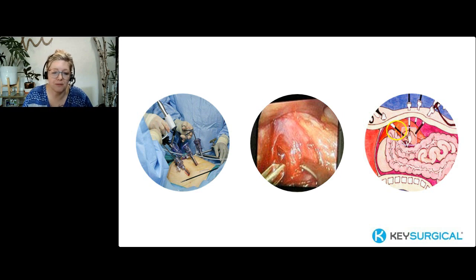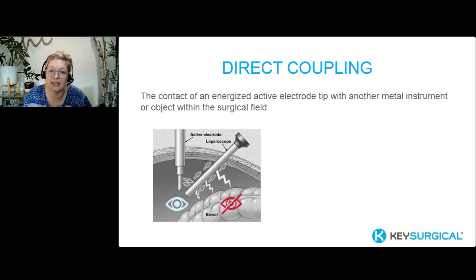So the first complication for coupling that we're going to talk about is direct coupling. And this is the contact of an energized active electrode, the instrument that we're using, right, with any other metal instrument or object in the field. And so why it's important to remember that there's different people holding different instruments. They might not know if they touch, or they might know better, right, if they touch. So that's kind of a conversation that we can have together as a team. Sometimes we do this intentionally when the surgeon says, buzz me, or apply that tip to a clip, right? So we're heating up a metal clip, and then we kind of do a little electrocautery with our electrosurgical device. So this is kind of the importance of that.